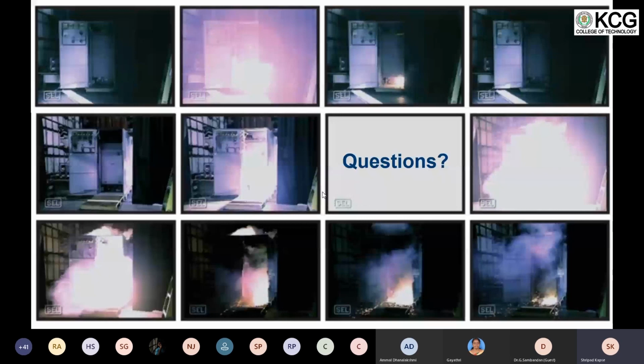But here we are talking about the hazards that occur on the switchgears or switchboards, where you would find most people working very closely. So we are talking about ways to mitigate switchboard related hazards, like a bus bar fault or a phase-to-phase fault in the switchboards. And here we need to take into consideration the maximum voltage fault currents and the DC offsets that may be associated. I hope that answered your query, sir.